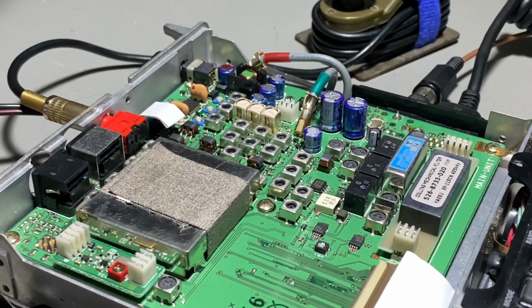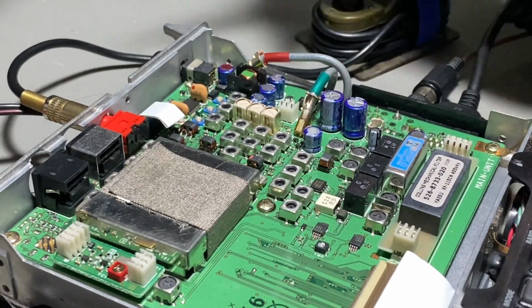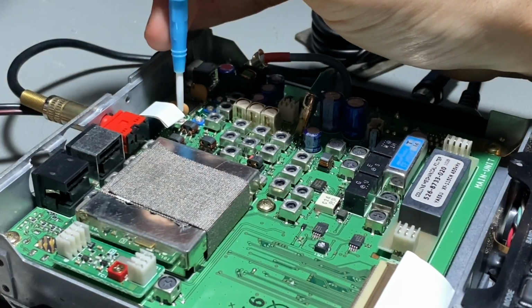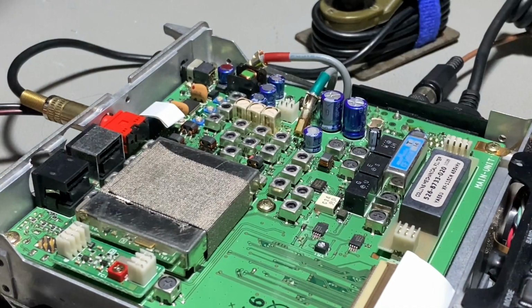So 88 megs, you turn the generator on, the frequency, the modulation on. You can hear the tone very well, and the SINAD I'm having is 51.5. And basically, you take a small screwdriver, you go in here in the trim cap for the best SINAD. And once you have found the best SINAD, you're done with this step. So we switch that off, and that's another step done.